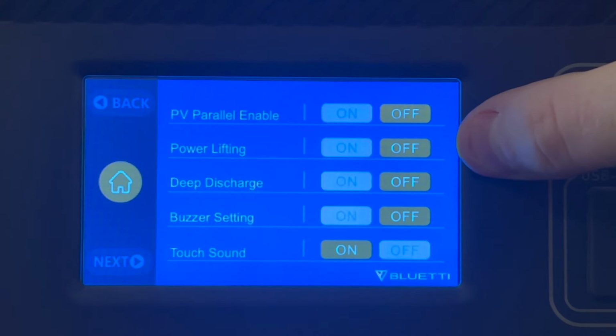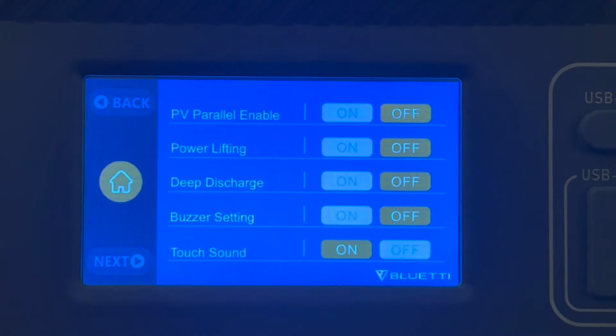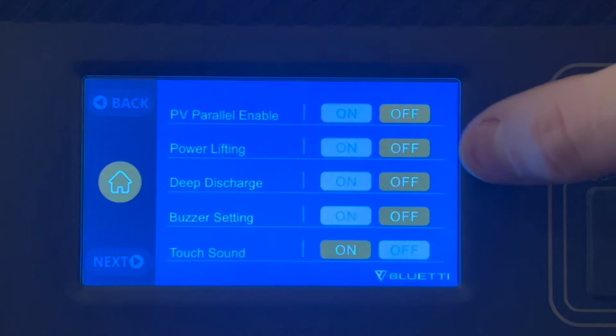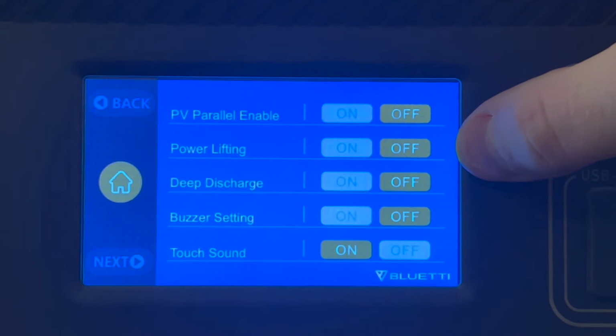It's got powerlifting mode, just in case 5,000 watts isn't enough for you. Powerlifting mode is used for resistive loads only. It is not helpful for motors. So if you've got a sump pump that needs more than 5,000 watts, this is not going to help you. This is for things like heaters. This is for stuff that is a purely resistive load, light bulbs, heaters, stuff like that. Okay, this will absolutely destroy your microwave. So I would leave this turned off unless you really have a load that it's specifically needed for. The 5,000 watt inverter is really big.